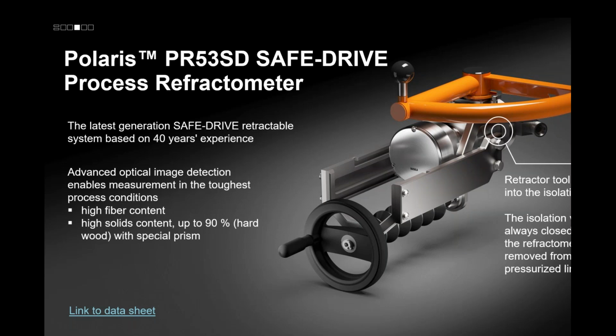This here is the safe drive attached to a sensor. It allows you to insert it into the process and remove it, as the name suggests, very safely. There are some very aggressive chemicals involved, high pressures, and super high temperatures. This is a perfect example of why you'd want an inline refractometer versus taking samples—not only for better control and instantaneous readings, but also for safety, which is very important in pulp and paper. This is a mechanism for pulling it out of the process while it's running, basically a hot tap with a lot of safety engineered in to keep operators safe from hot process or chemicals being sprayed on them.